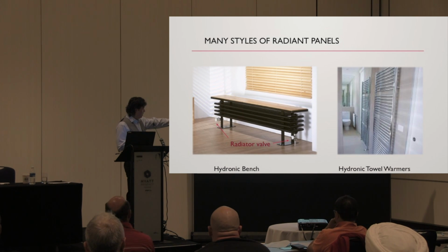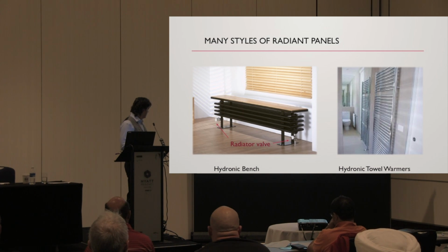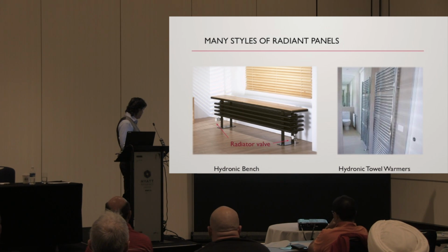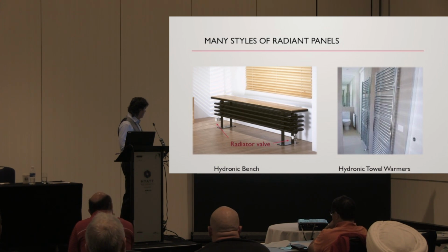There's towel warmers. That's one way to do it. I thought this thing was kind of cool. Hydronic bench. If you look right here, there's your balancing valve, and that's what's called a thermostatic actuator right there. So it's sensing the room temperature, so you just turn that thing to whatever you want, 20 degrees C, 70, and it modulates the flow of the water through there. So that's just one big radiator. There's all sorts of sizes and shapes.